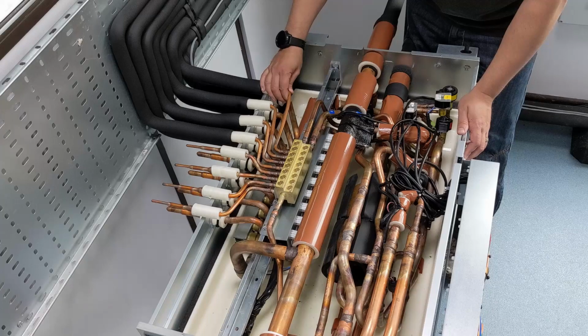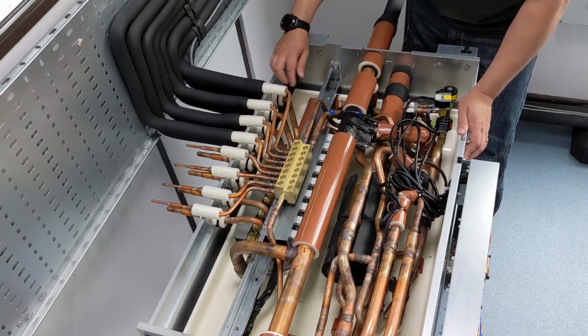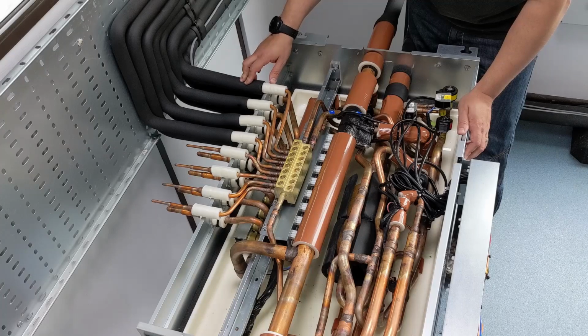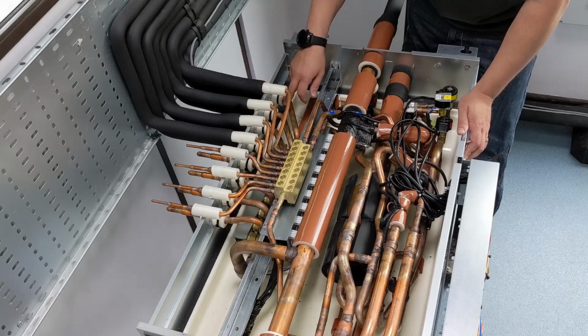We've got that big pressure drop, at which point it's now trying to boil at around about 0 degrees evaporating temperature, because we aim for that. That's how the compressor is being controlled. So 0 degrees evaporating temperature, or around about 7.2 bar. Passes through the expansion device on the indoor unit, boil it all off from being a liquid to all being a vapor, and we've got the vapor coming back.